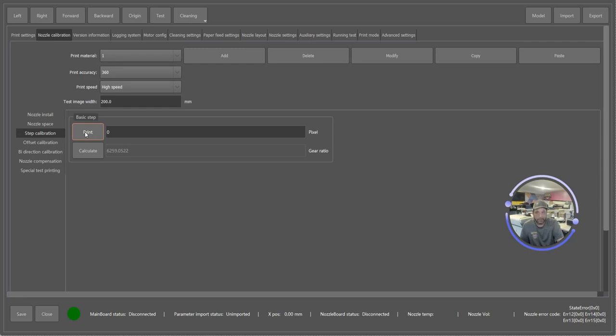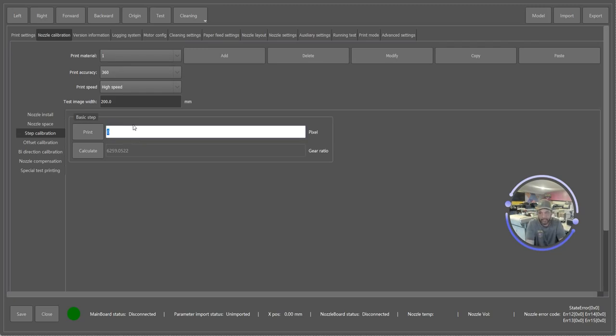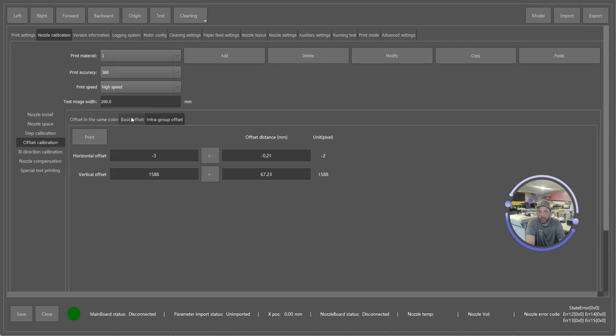What we would do is print out the chart, see what number correlates to the right setting, which I'll do another video on. We will change that. If it says that the nicest setting is +2, we'd hit the 2 button, we'd hit calculate, and then we'd hit save. Very important, you have to hit calculate and you have to hit save. The next most important is our intra-group offset. So we go offset calibration, intra-group offset. You can print your test, check it out from there.